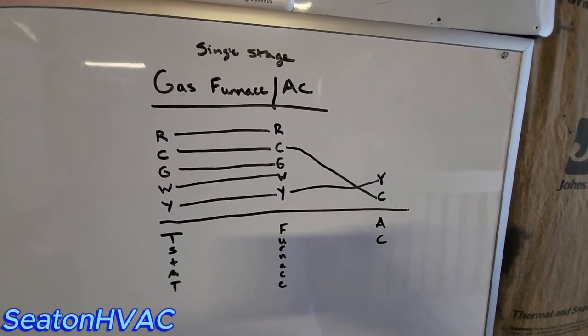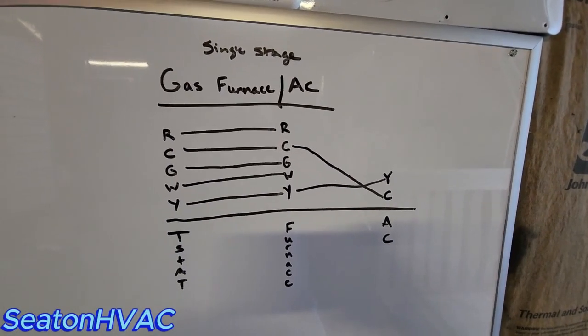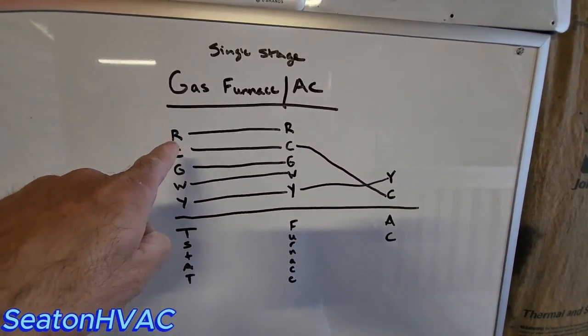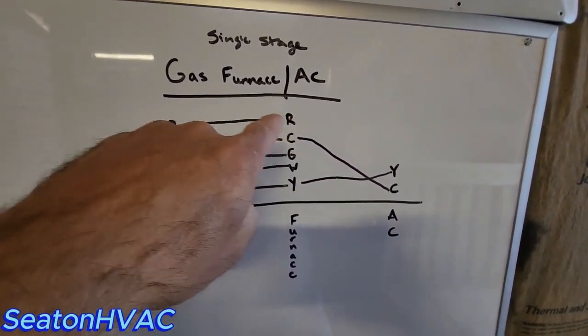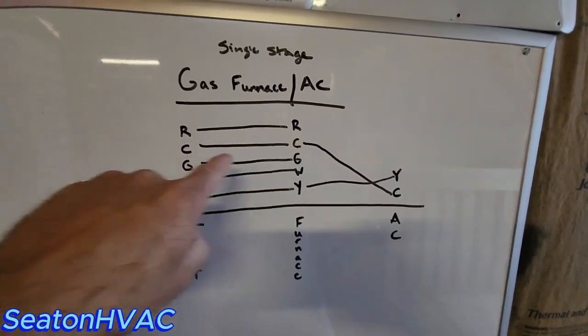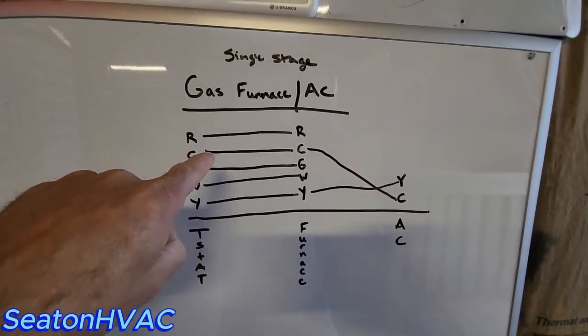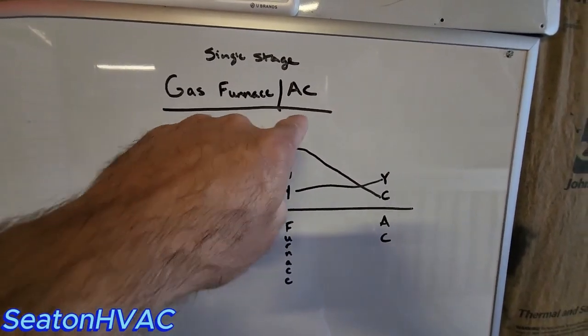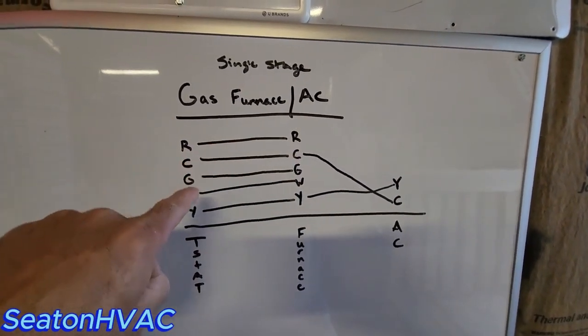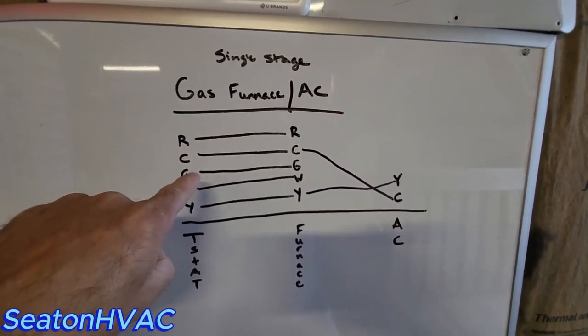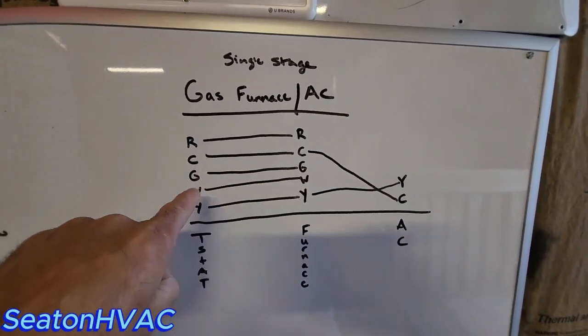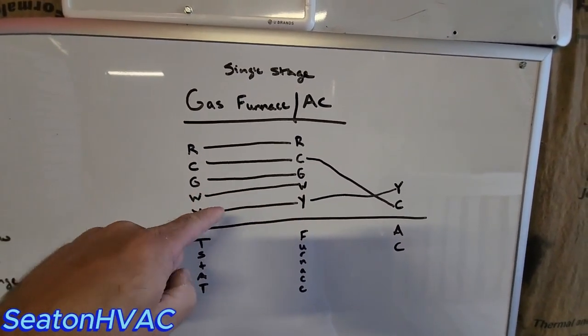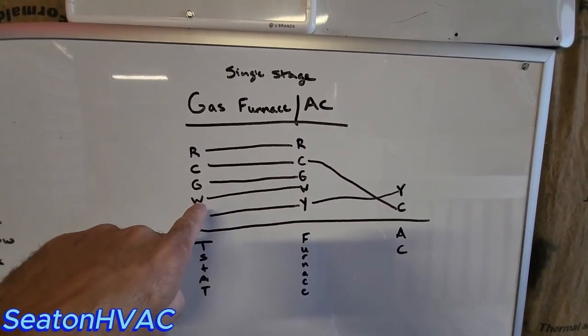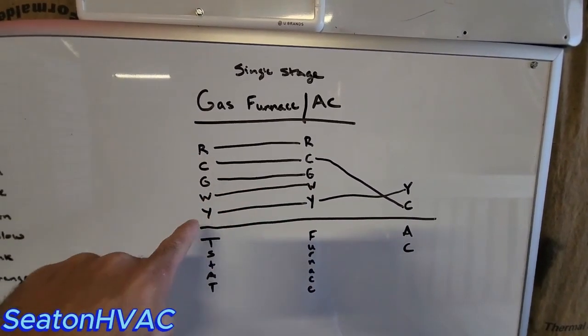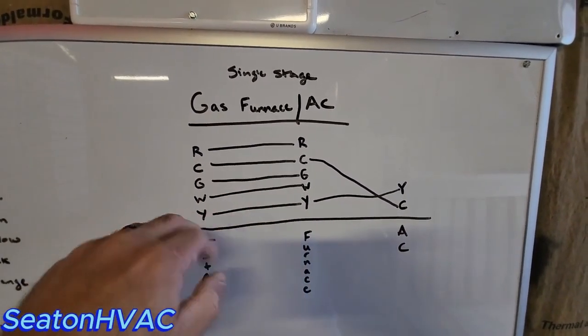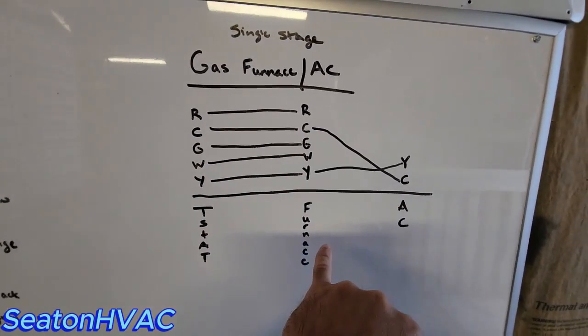Okay, guys, single-stage gas furnace with a single-stage air conditioner. Very basic. Red to red, that's your 24 volts hot. Common to common, C. I already showed you what colors these would be. So blue, that's your 24 volts common. G controls your fan, that's a green wire, G to G. W, W1, it's going to be W on a single stage unit. Just W to W, your white wire. Y to Y, yellow. So this is going from your thermostat to your gas furnace.